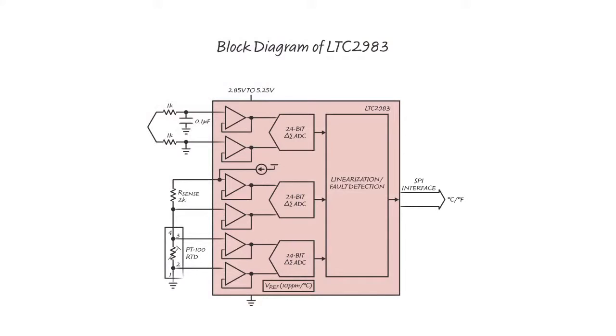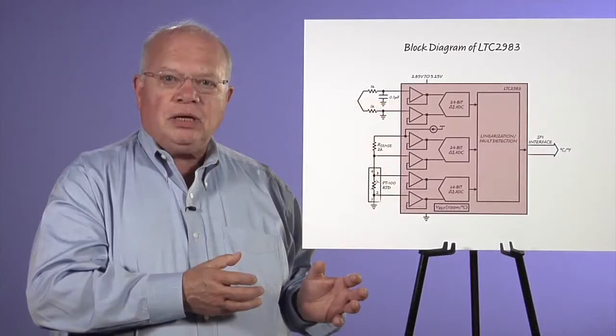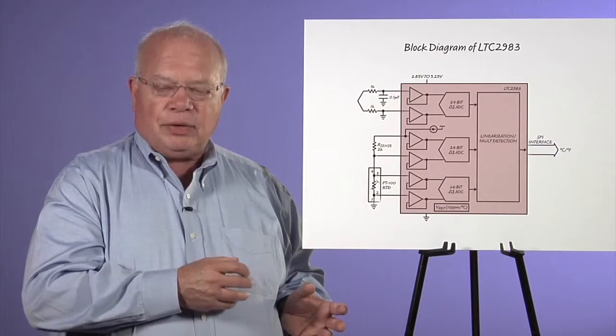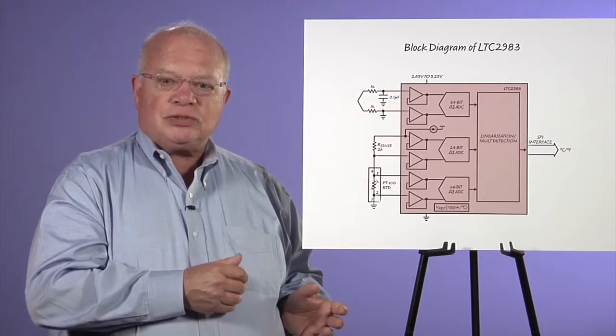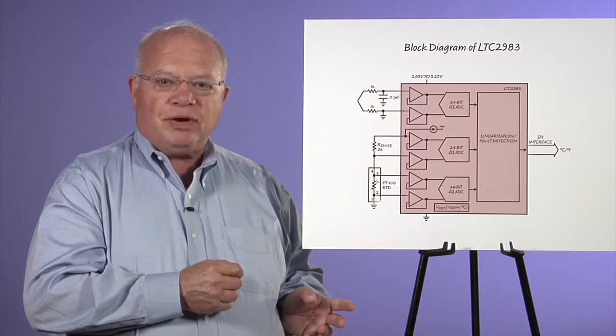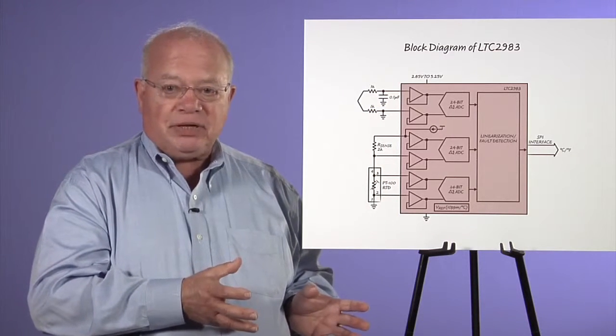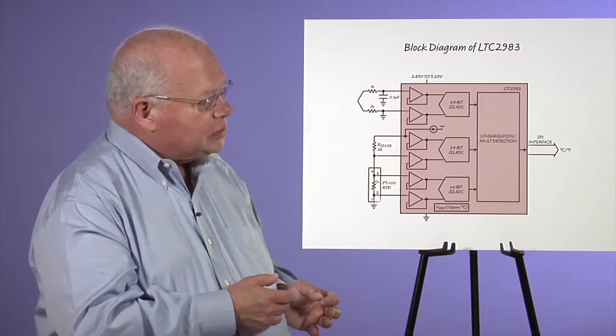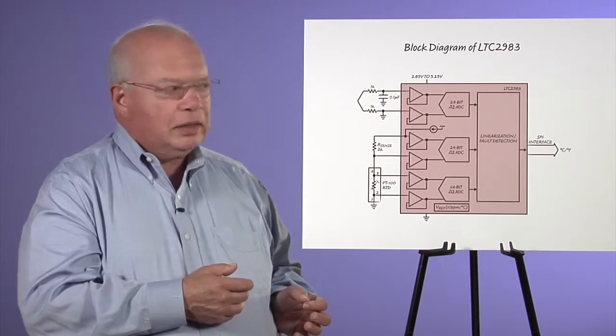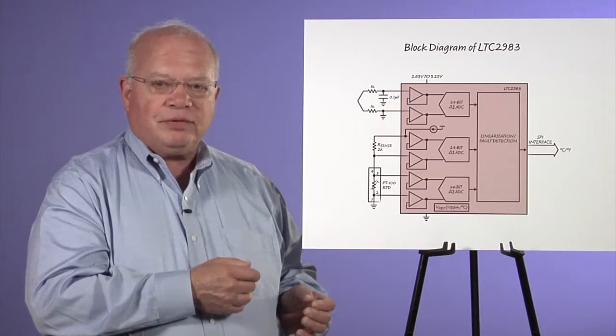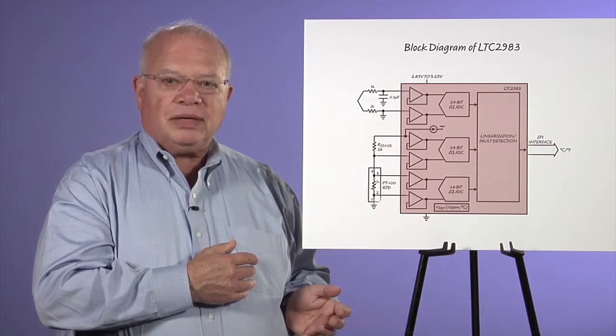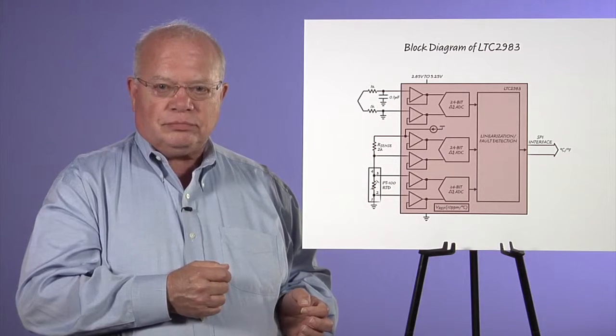This is a partial block diagram of the LTC 2983. We have three 24-bit A to D converters. We need these because of the very large dynamic range with thermistors. They're also auto-zeroed so that we can get accurate measurement of thermocouples. It has 20 inputs, so you can use them differentially or single-ended. Has a built-in voltage reference, and it has a big processor in there to take out all the nonlinearities. Inputs are buffered, so you don't have to worry about the 2983 loading the sensors.